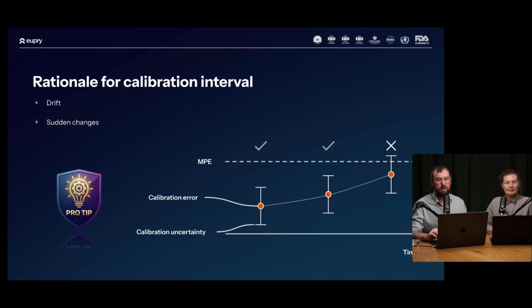So there's a good question related to this topic. Have you some experience or samples for drift, for example, with a PT100? I would love to say that PT100s are the same, but they are not. Just like cars, they are very, very different. PT100s have a very large susceptibility to the production process, and PT100 sensors are also very susceptible to mechanical shock. So it's actually quite funny that often PT100 sensors drift less and less as the years go by. They become more and more valuable because the drift tends to fade out and the drift per year becomes smaller and smaller. It is very, very different.